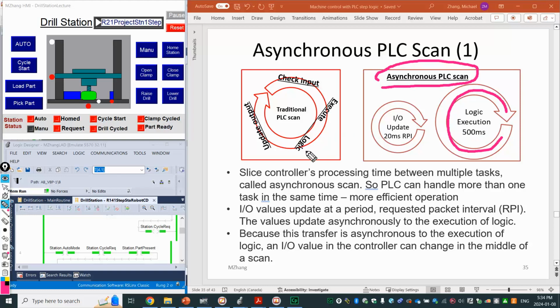So they use a dedicated controller or process to scan your logic, handled separately, which runs very fast and guarantees your logic is scanned even faster. At the same time, they may have a different controller or process dedicated to the I/O update. Before, all 3 steps were in one scan running in sequence - input, logic, output. But in the new setup, they run in parallel.